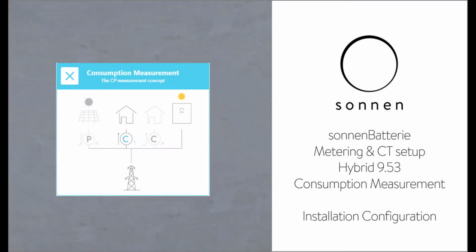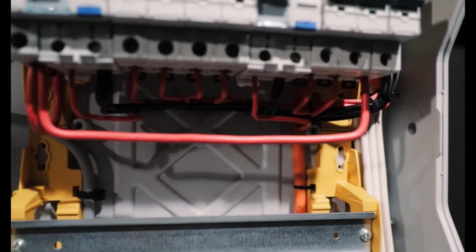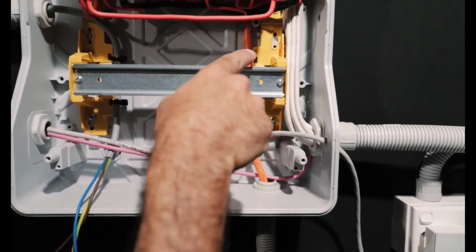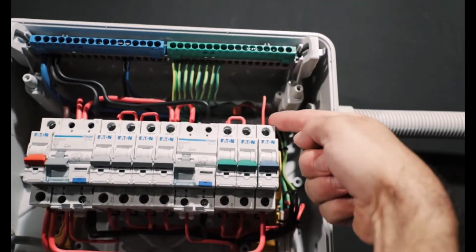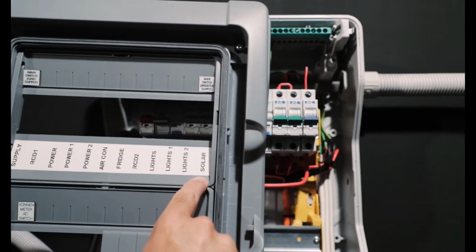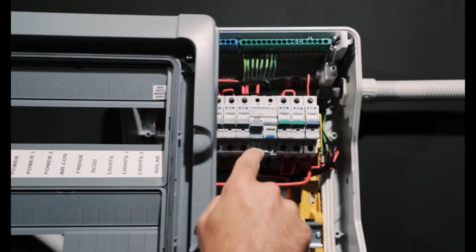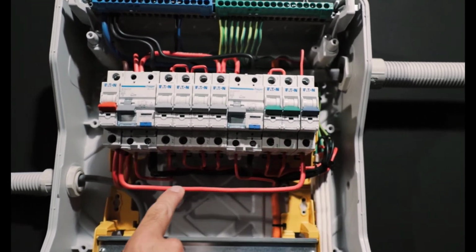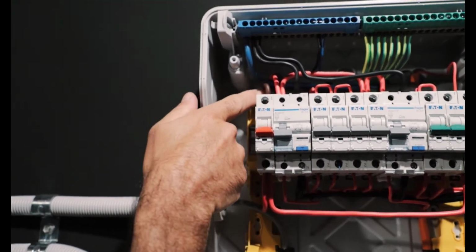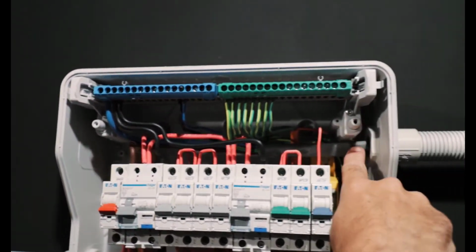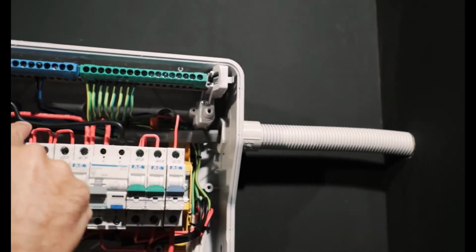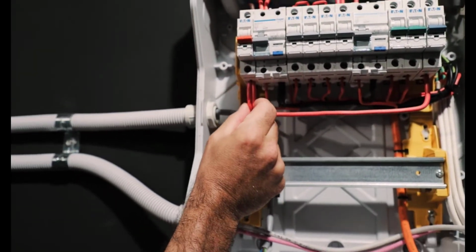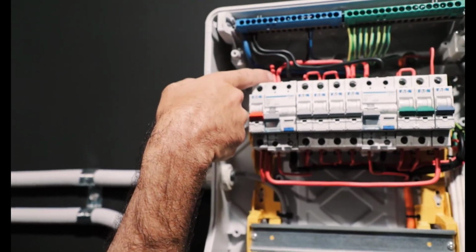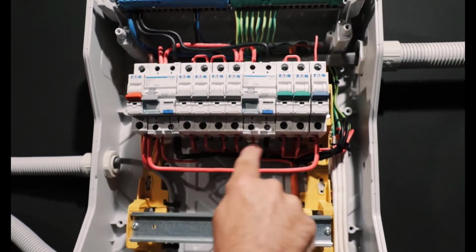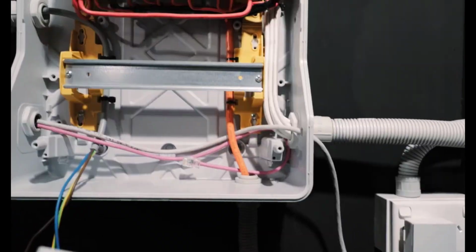Next alternative setup will be the consumption measurement. As a PV comes up, so this installation, you can see we've got the solar. Through the solar isolator, then the solar is in parallel to the grid supply. So we've got the grid supply, comes in here, the grid comes in, combined with the PV. We've then got a supply coming up from the output of the main isolator to all of the load circuits. So the load circuits here can be seen isolated to everything else.